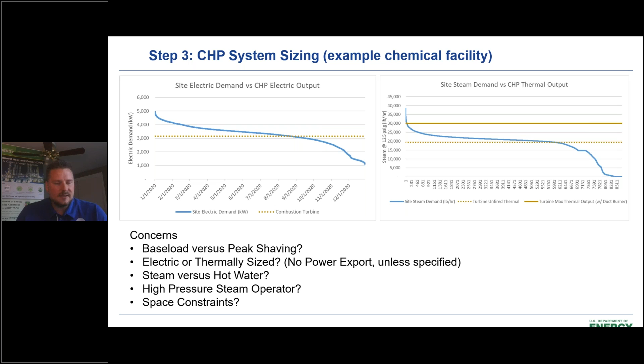And on the right-hand side, we're doing the same thing for the thermal demand. We've taken the site steam demand. On the left-hand side of the blue there, it's almost 40,000 pounds per hour at 125 PSI. And you can see to the right, there is a plant shutdown where basically we're not using any steam. That dotted yellow line shows 20,000 pounds per hour of steam generation with a turbine that's unfired. If we're firing it, this system could provide up to 30,000 pounds per hour. So now we're starting to match up what specific CHP system we can match for your facility. Again, at a high level estimate. Next slide.